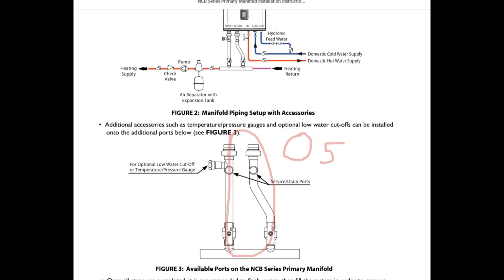About five gallons per minute, let's say. And then you have your secondary loop, which an external pump will control. And that will be the loop that goes up through all the baseboard, through the radiators and back around again. So this loop, let's say, will be about 20 gallons per minute. This loop, the primary, will be five gallons a minute. So basically what's happening here is that this circulator pump is allowing water to get pulled in off of this 20 gallon per minute loop here, heat it up and inject it back in again.